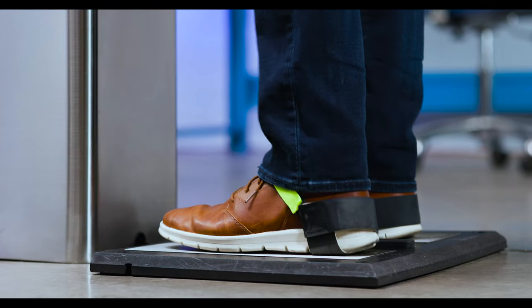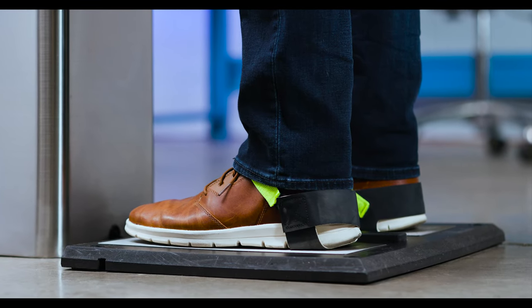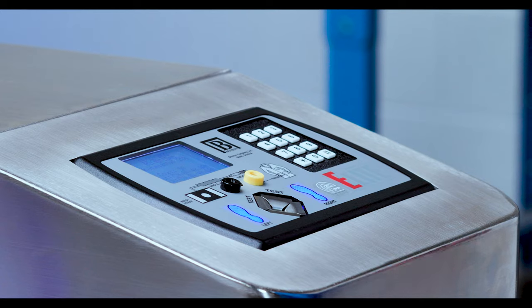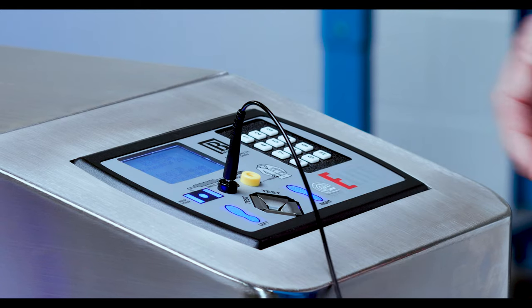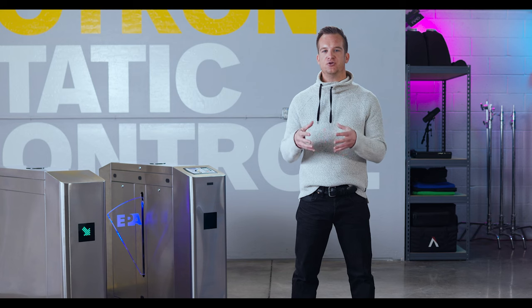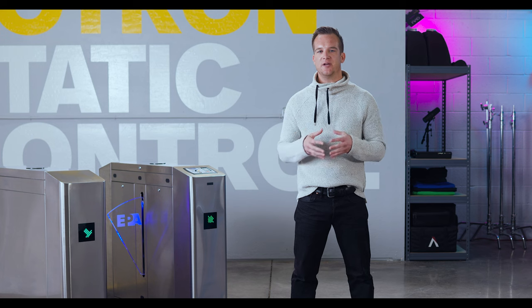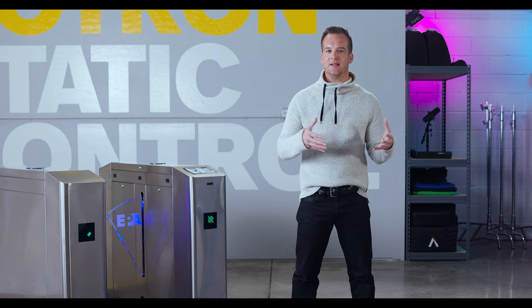This will query your name and your test requirement, so pay close attention to the display on the Elite. When testing footwear, step onto the footplate and make sure your ESD footwear is all the way on the metal. When testing the wrist strap or smock, carefully insert the coil cord into the corresponding input. As you do this you may notice that the LED indicators will illuminate blue, to let you know that your device has been detected by the Elite.